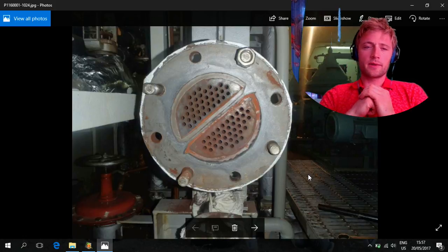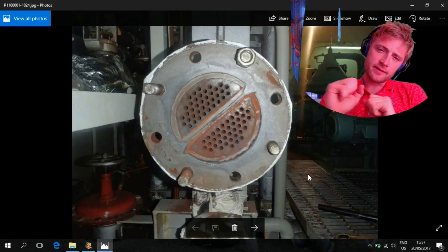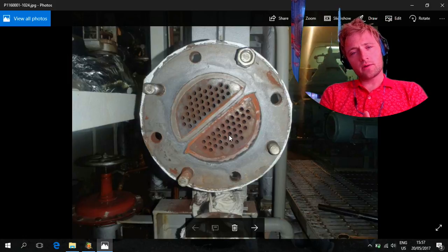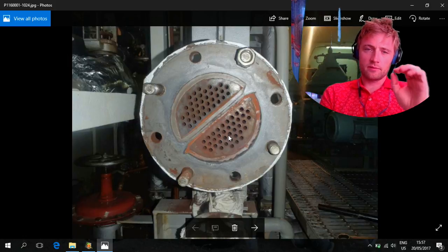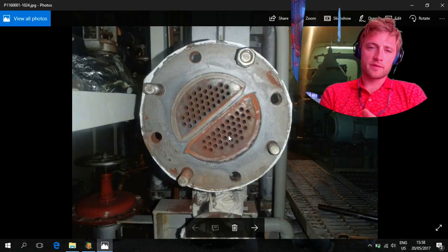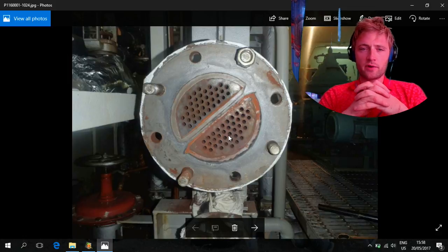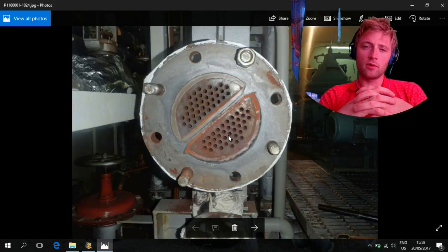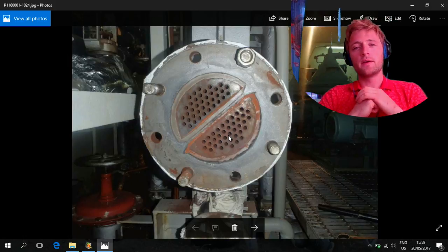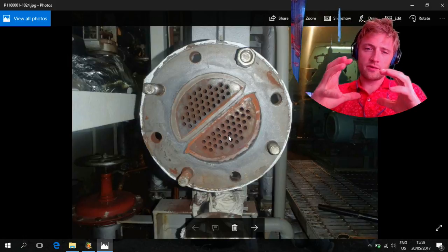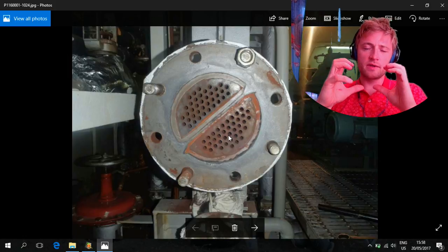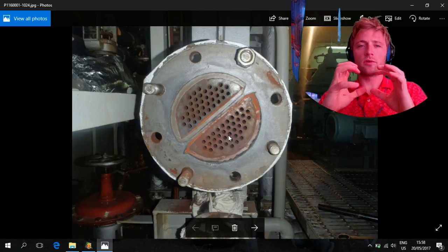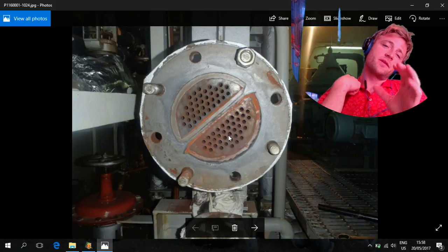The steam is passing inside. This is the inlet side and the outlet side. The steam goes inside, there are some tubes which travel and transfer heat to the oil. The oil is passing outside, so there is not any contact with steam and oil. We don't want steam coming to our oil.